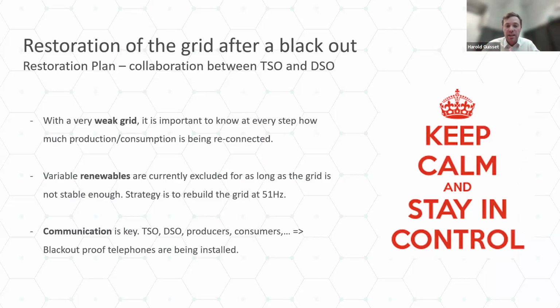And that is why within ELIA, we now have a plan to do the restoration at 51 Hertz if we do the bottom-up restoration, because at 51 Hertz, small units like solar panels and wind would not be allowed to reconnect. So they would not reconnect automatically. And so we would avoid renewables for as long as possible and only reconnect renewables once the grid is stable enough.